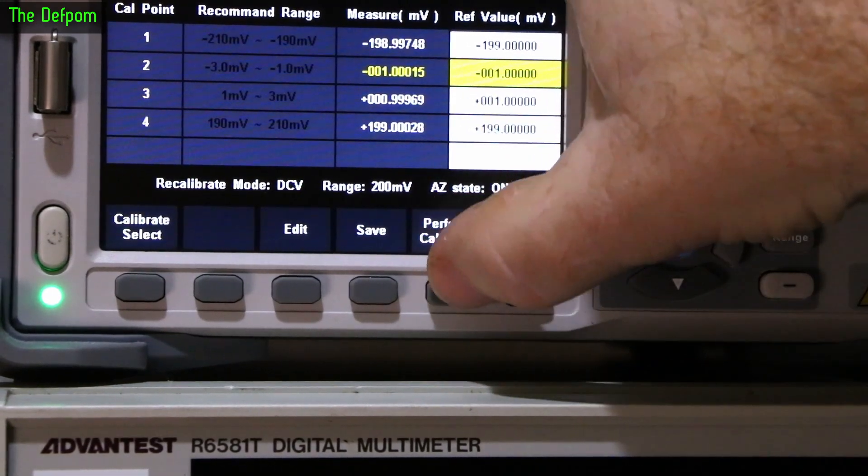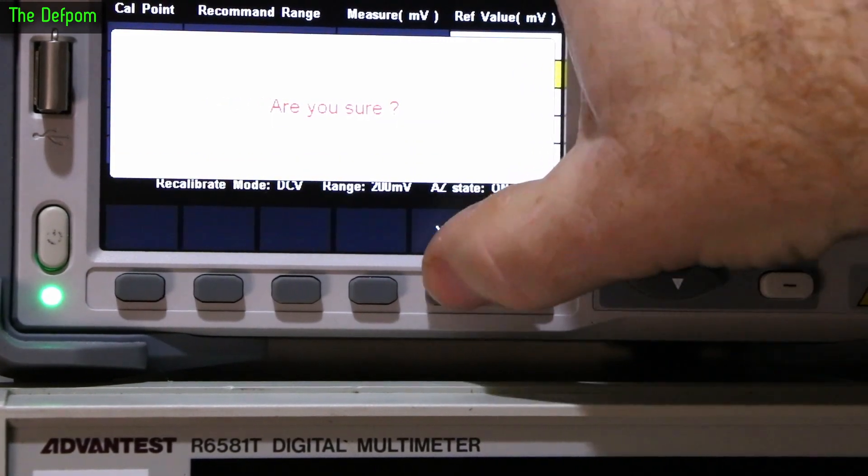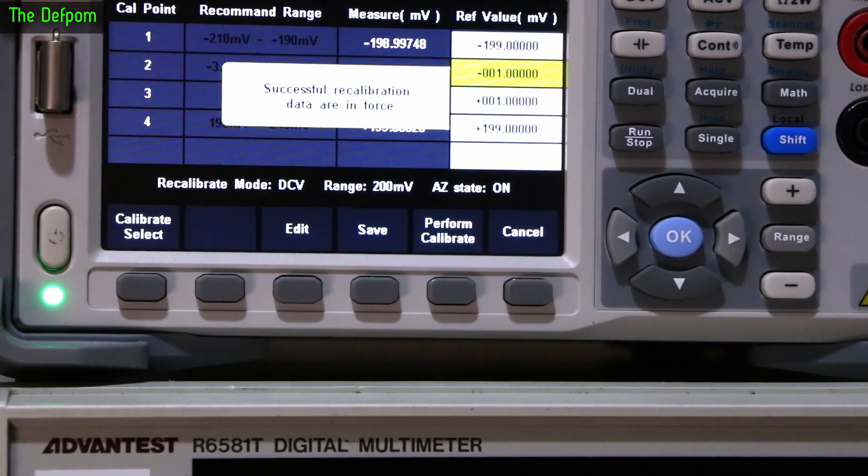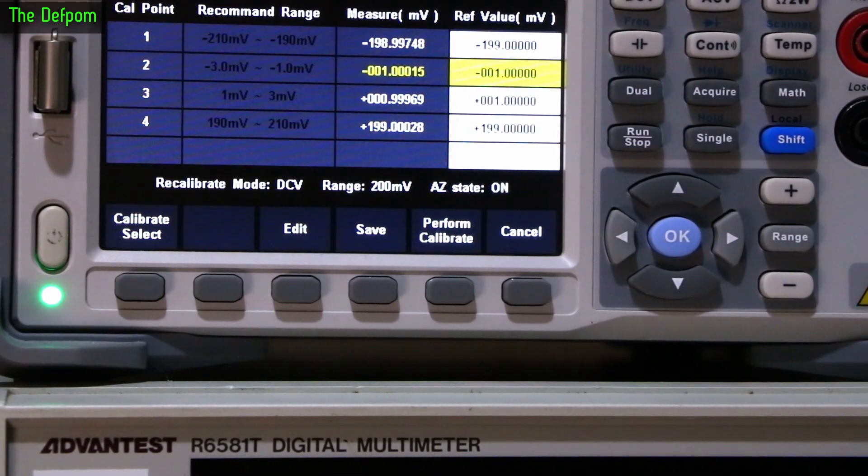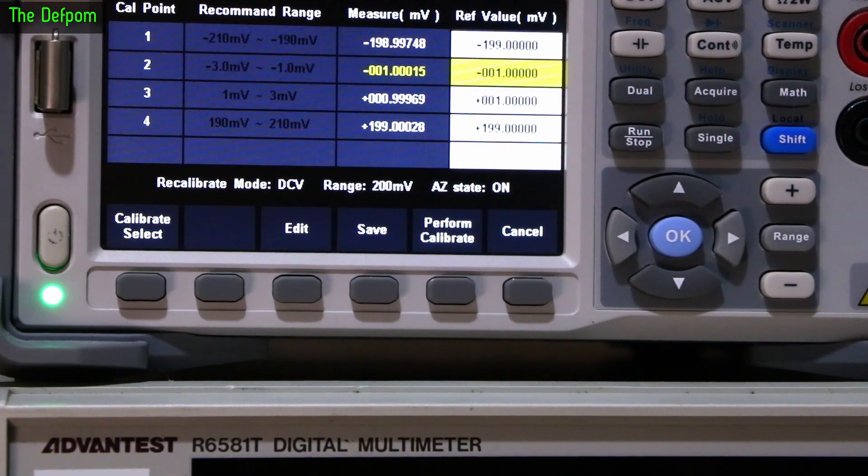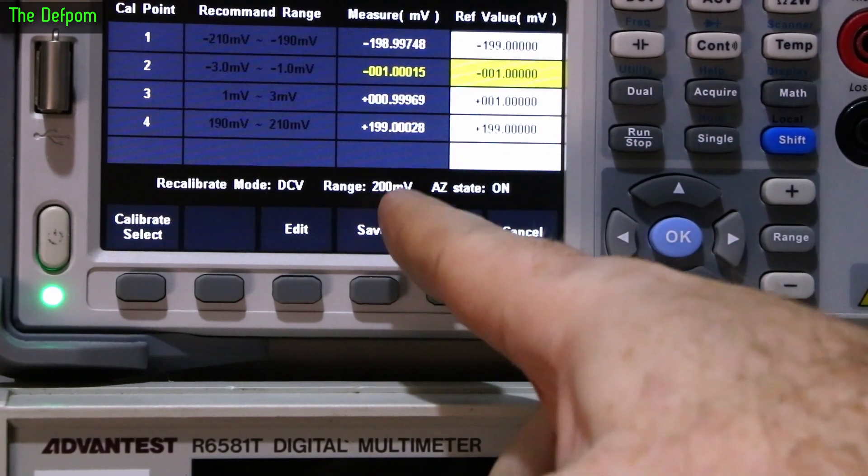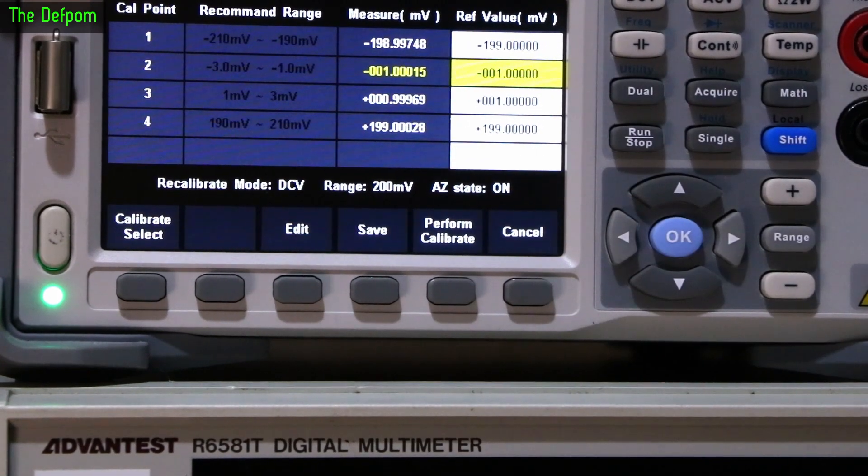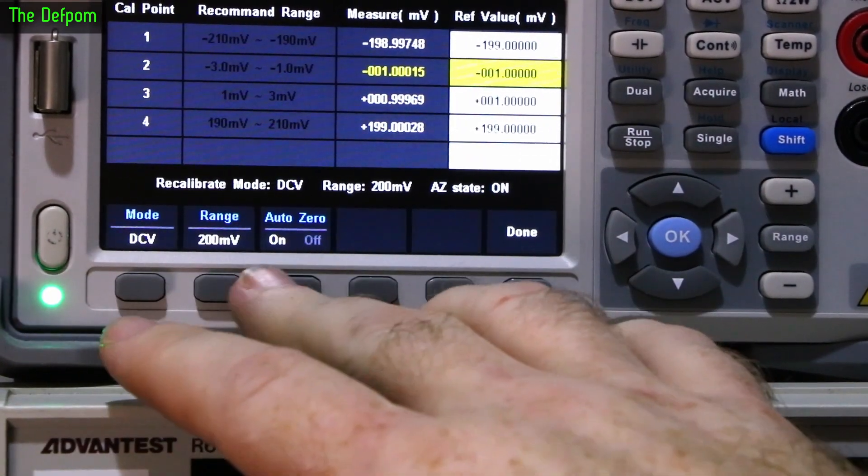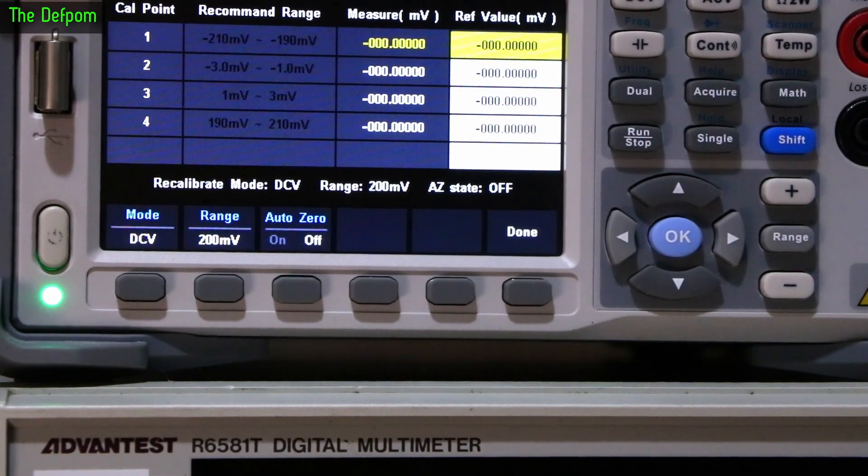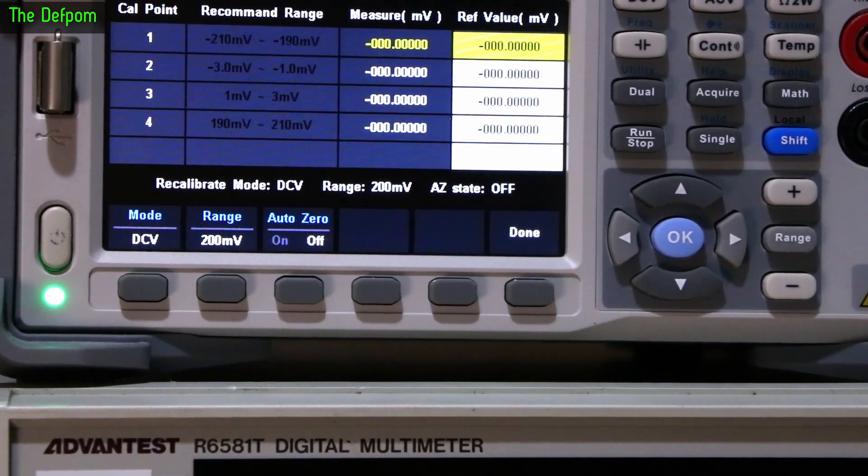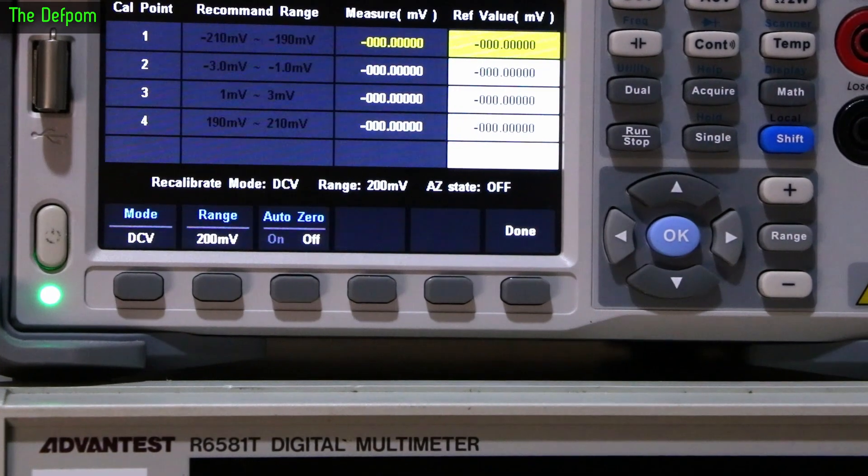Now we do perform calibrate. Am I sure? Yes. Data was in force apparently. So that means it should now be reading correctly in all the particular modes. Auto zero on and the 200 millivolt range is now calibrated. We have to repeat this now for auto zero off. That will calibrate the 200 millivolt range completely.